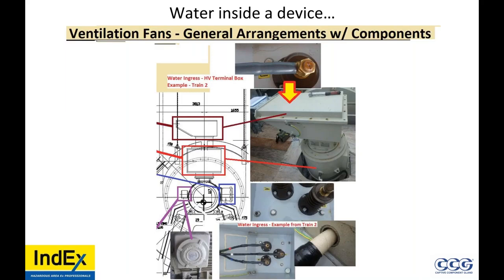So would we say that the water ingress affects the EX protection technique? Well, this terminal box is EXE. Water causes problems with creepage and clearance distances, arcing, sparking. Certainly IP ratings have a very important effect on EX protection techniques.